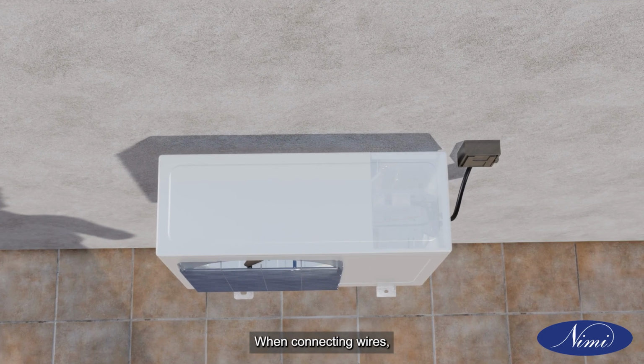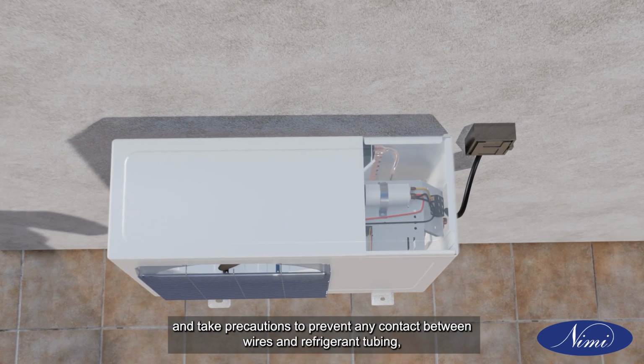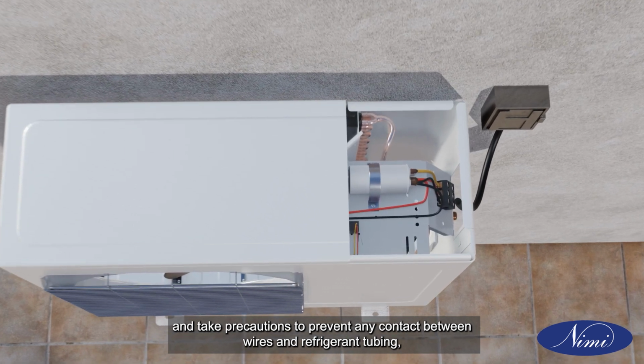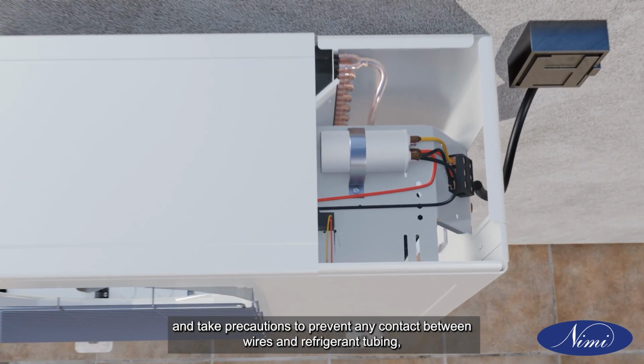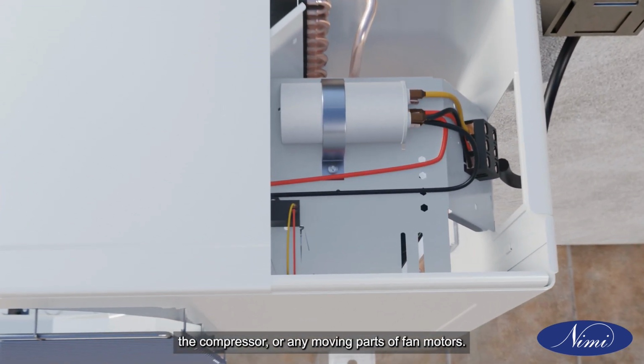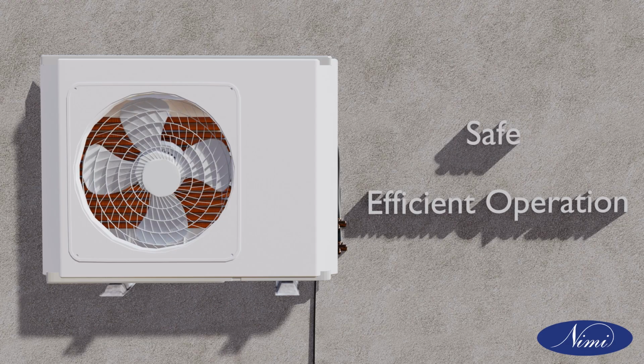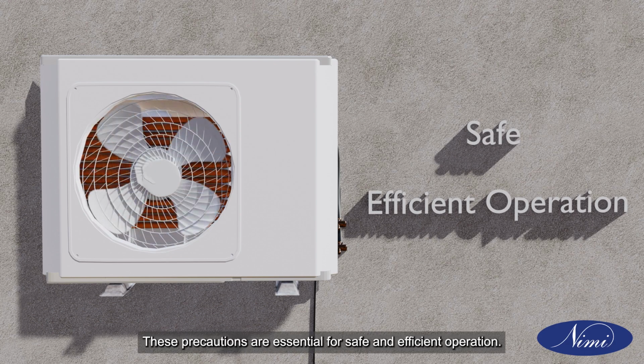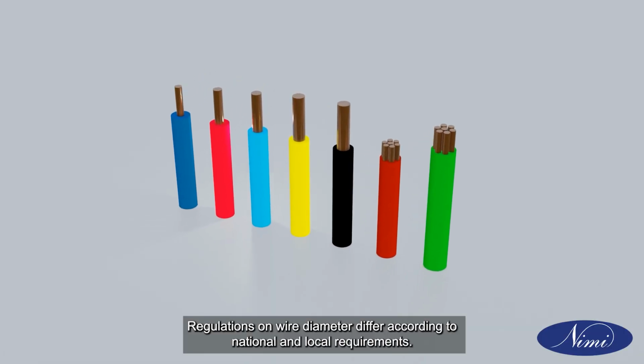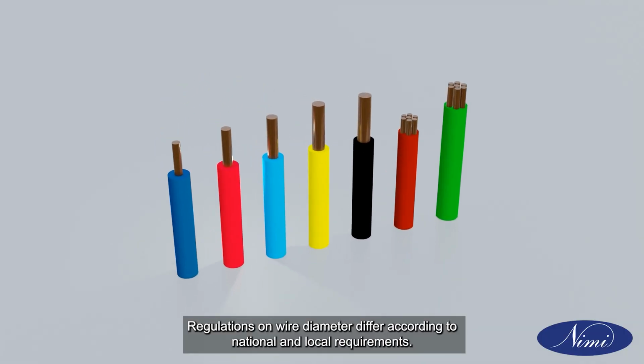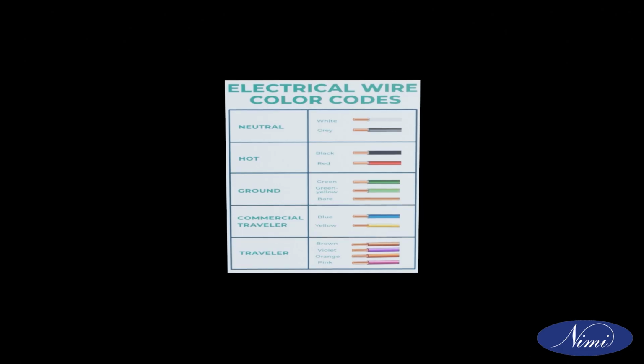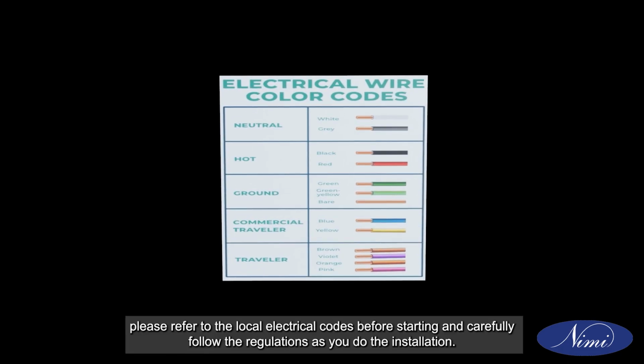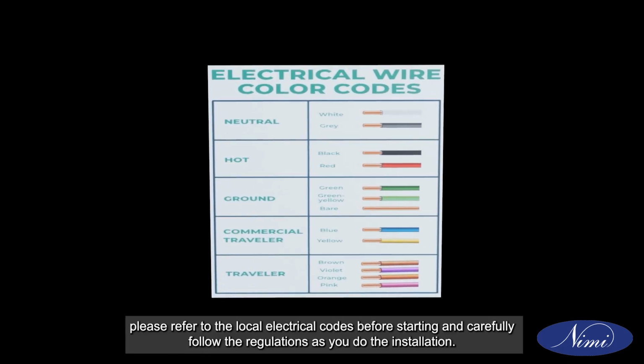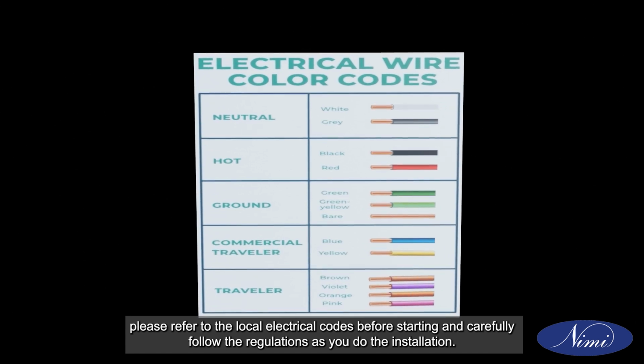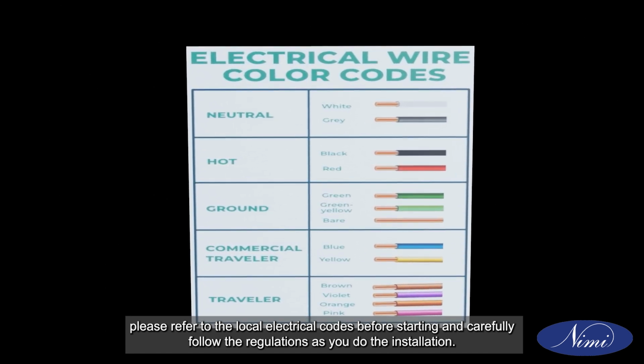When connecting wires, ensure they are firmly secured and take precautions to prevent any contact between wires and refrigerant tubing, the compressor, or any moving parts of fan motors. These precautions are essential for safe and efficient operation. Regulations on wire diameter differ according to national and local requirements. For field wiring regulations, please refer to the local electrical codes before starting and carefully follow the regulations as you do the installation.